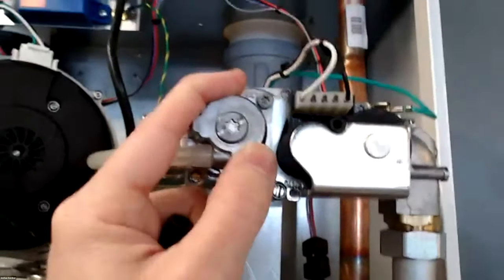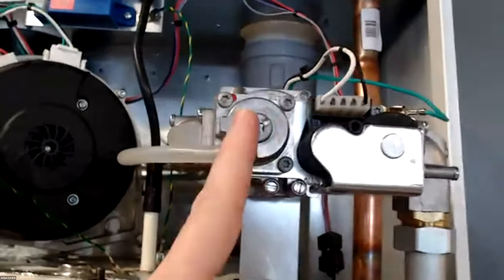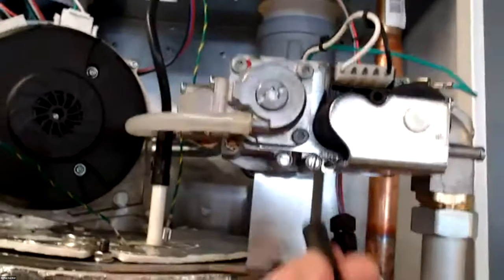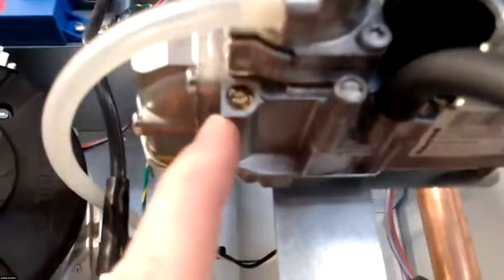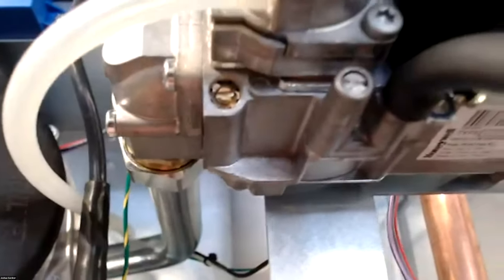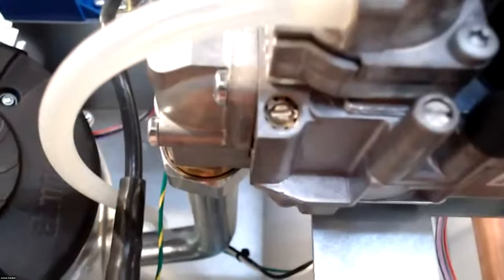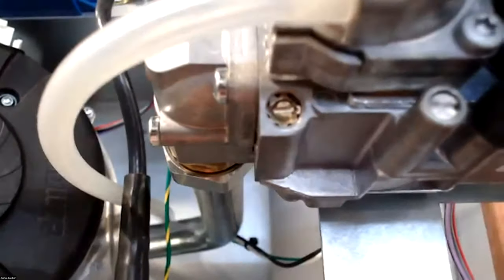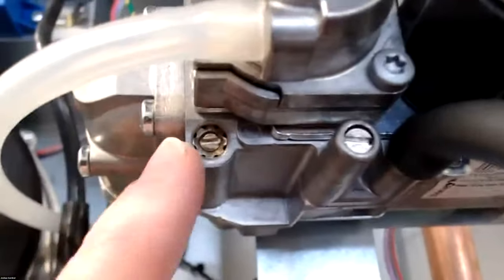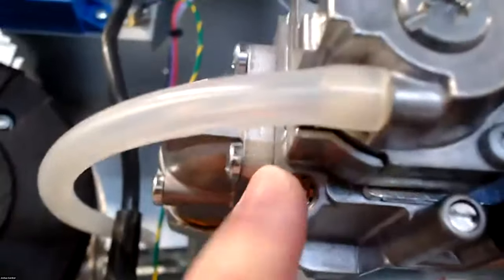I'll show you guys exactly some of the things that we're going to explain to you. But this is really delicate. We've got to be careful. We don't want to turn too fast and too much because we can damage that diaphragm and those springs in there. Underneath here, this little brass screw right here, flathead, that's our throttle. So that's going to be our adjustment. Not super sensitive. You could turn it a full turn and maybe watch it drop 0.5. So this one, you don't have to worry about messing anything up. If you do it too fast or too slow, it's pretty forgiving on that throttle unit.